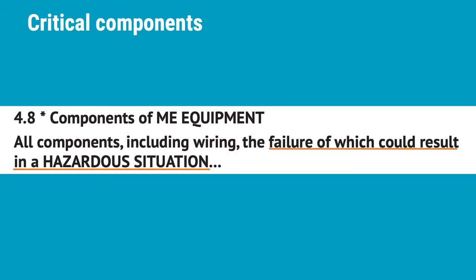While there is no formal definition of critical components, the text of IEC 60601-1 provides an informal definition, which is all components, including wiring, the failure of which could result in a hazardous situation. So you shall apply your risk management process to identify which components are critical components.